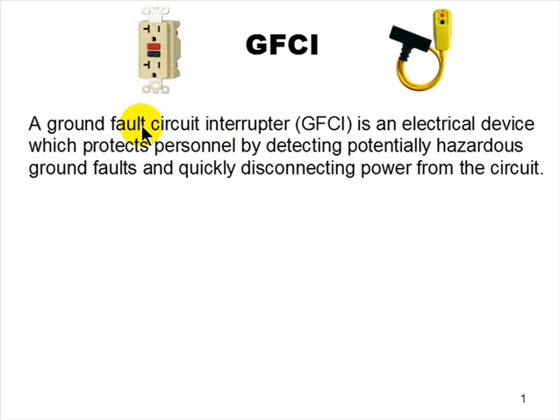GFCI, or as you probably know and love it, GFI. It's a ground fault circuit interrupter, GFCI. All right, you can have the receptacle type. You can buy the inline type. You plug it into your extension cord or whatever, and then plug the device into that. It's an electrical device which protects personnel by detecting potentially hazardous ground faults and quickly disconnecting power from the circuit.